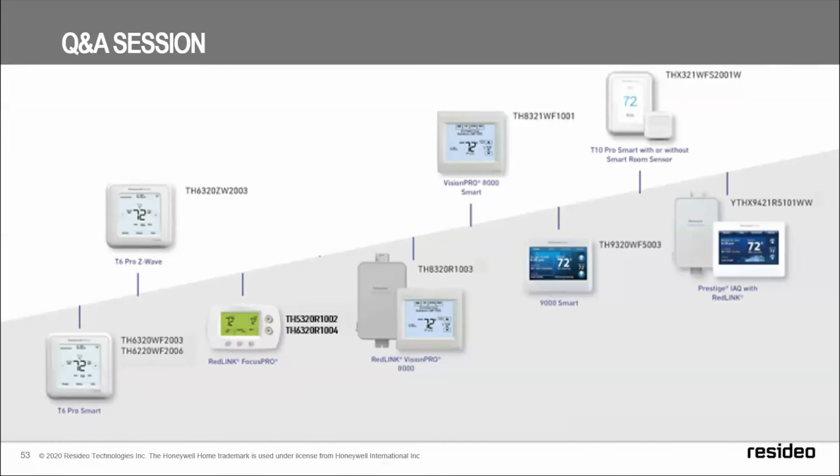In the past, and in certain models and applications still currently with a heat pump system, if we manually adjust that set point, let's say increase it by 4 degrees, the droop won't kick in because the room temperature didn't droop by itself. We manually created that by increasing the set point. So we will still run the heat pump. And if we see a time to temperature rise and we're making progress with the heat pump, it'll stay in heat pump mode.